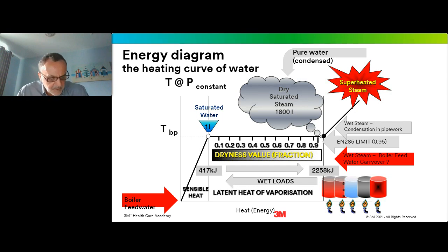Dry saturated steam will be pure because it's basically vapor steam without any liquid water present. But if there are any entrained water droplets present in it, then these could be contaminated with organic contaminants, such as the filming amines that the engineering community might use in their boiler and steam distribution systems. Or it might contain endotoxins or inorganic ions, such as iron or heavy metals, which might come from the non-stainless steel pipework, which is often used in house steam distribution systems.